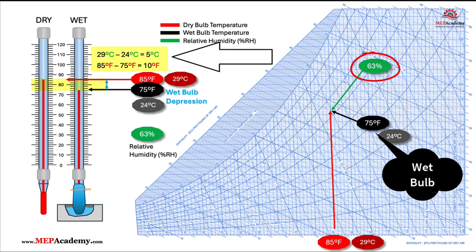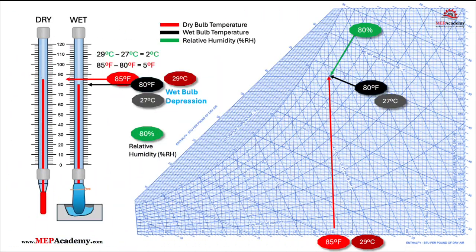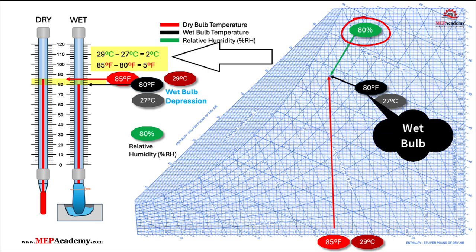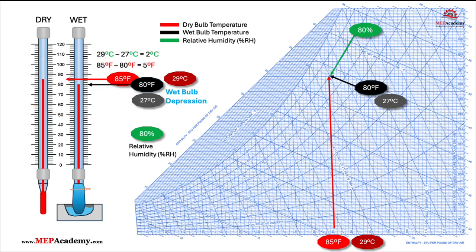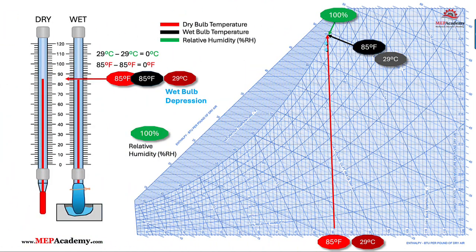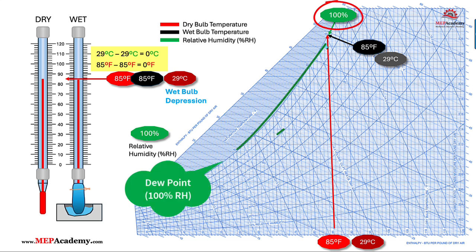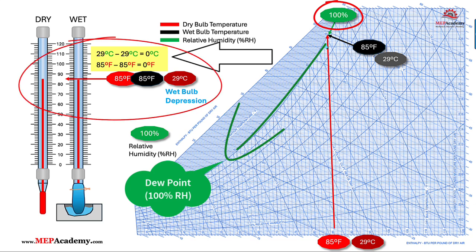What will happen when the wet bulb equals the dry bulb temperature? What will the relative humidity or dew point be? With a 5°F (2°C) wet bulb depression, the relative humidity has reached 80% at an 80°F (27°C) wet bulb. We can see there is very little wet bulb depression, and at this point swamp coolers are worthless, as there is very little room for more evaporative cooling. When the dry bulb and wet bulb temperatures are the same, we have 100% relative humidity and have also reached the dew point line where condensate occurs. The wet bulb depression is zero.